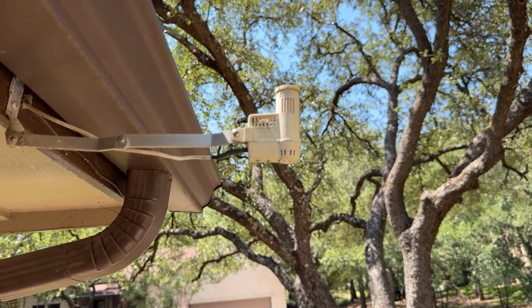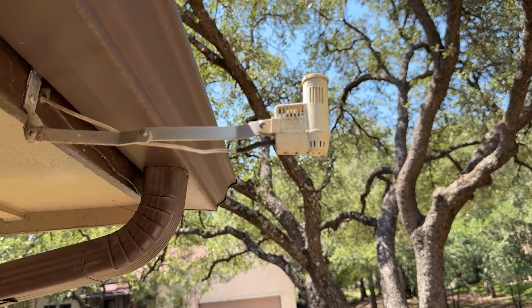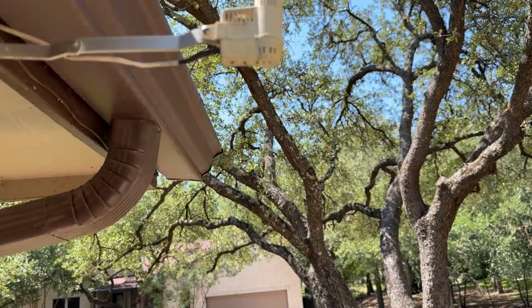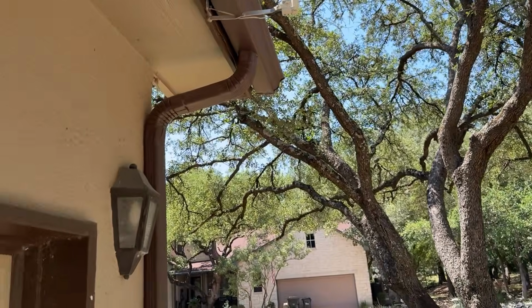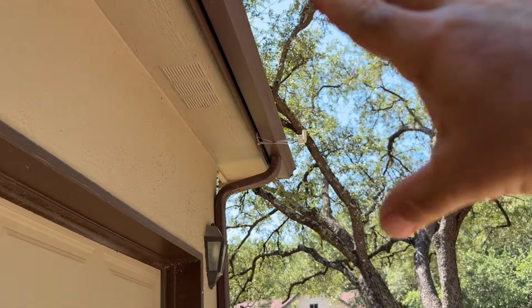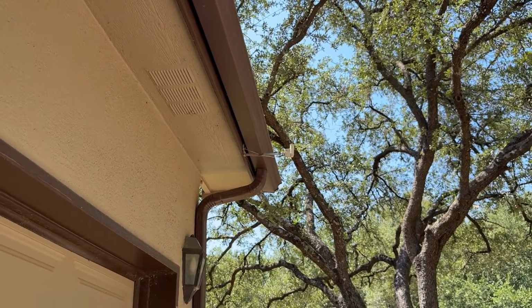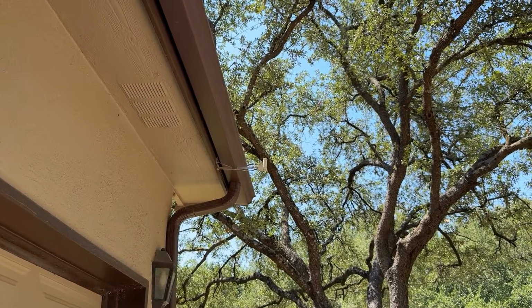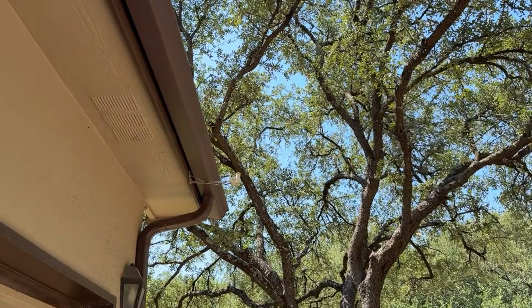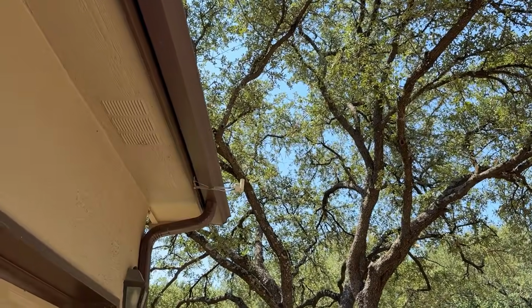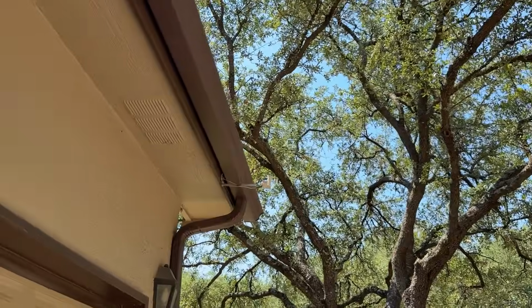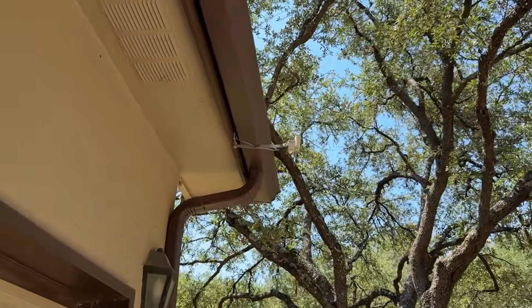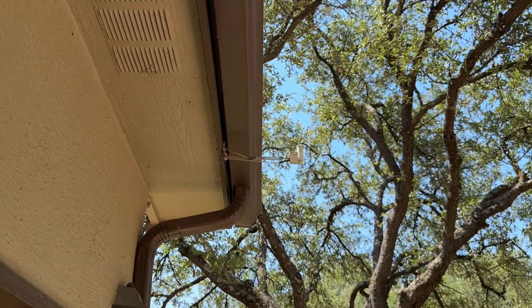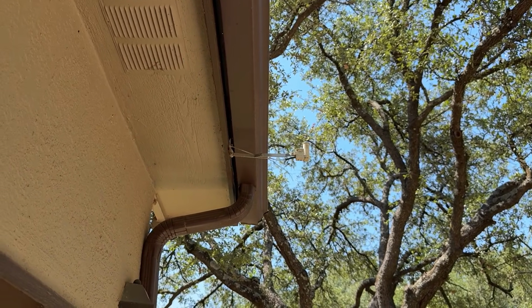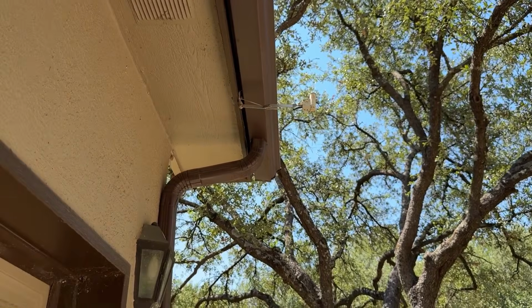and they will force a little plunger to make a connection, which then sends the signal down the wire to the control panel and tells the system, hey, we've got enough moisture, we don't need any more, and it will shut the system down and prevent it from operating until those discs dry out. Now, they often have an adjustment on there, so you can select, say, a 1/4 inch of rain, or an 1/8 of an inch of rain. I'll tell you, they don't always work perfectly, but we do need to see that device in place and make sure it's part of the system that we're inspecting.